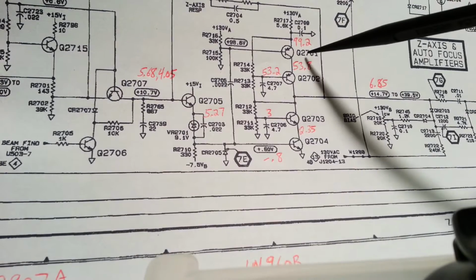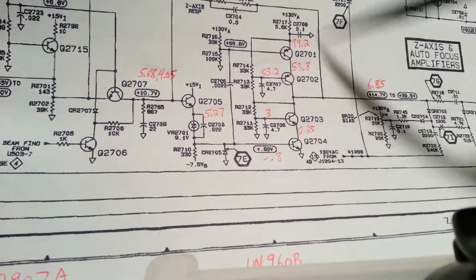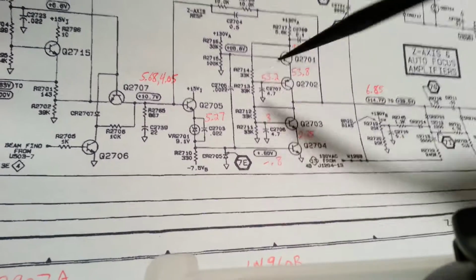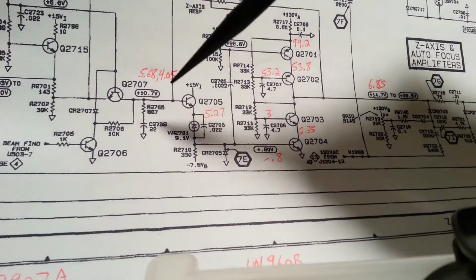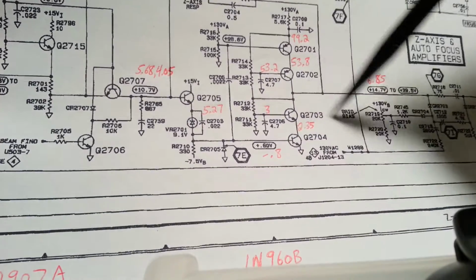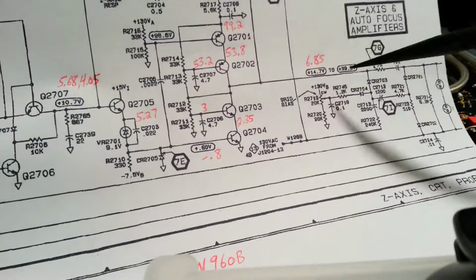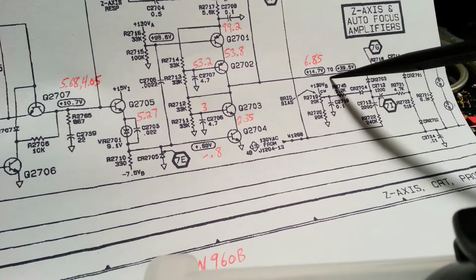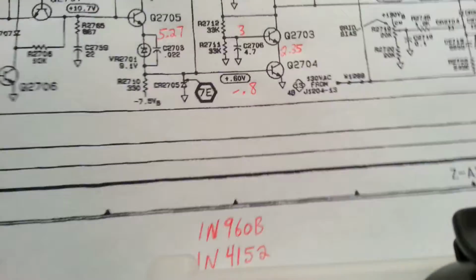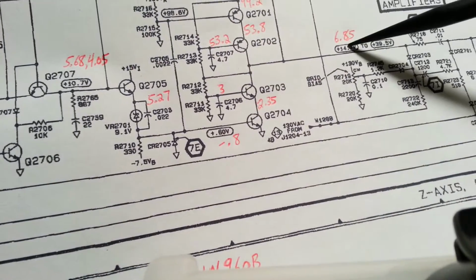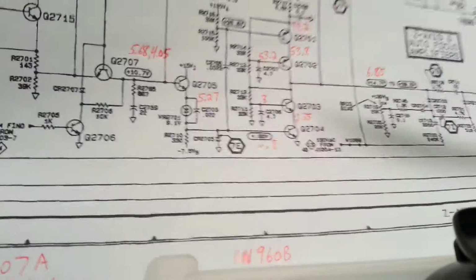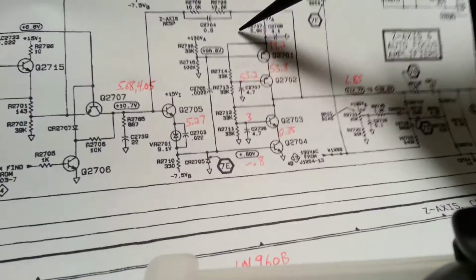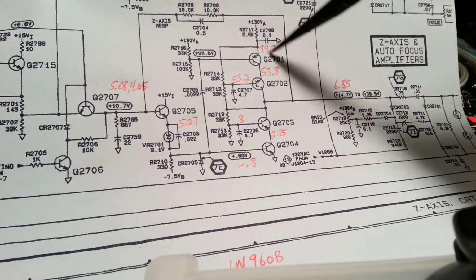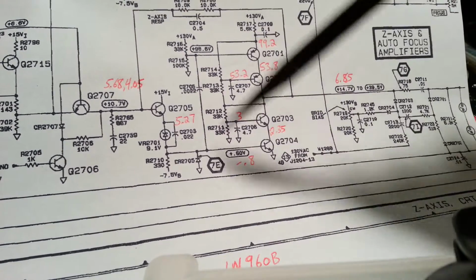So this region here, as David mentioned, this is a transimpedance amplifier, and this converts the current input, which is on this side, to a voltage output. And the output of this voltage should be reading in the range of 14.7 to about 40 volts. That's clearly not the case. We're measuring somewhere around 7 volts, so something's going on here. And I would say something has blown, possibly in this region right here. This is the Z-axis region.